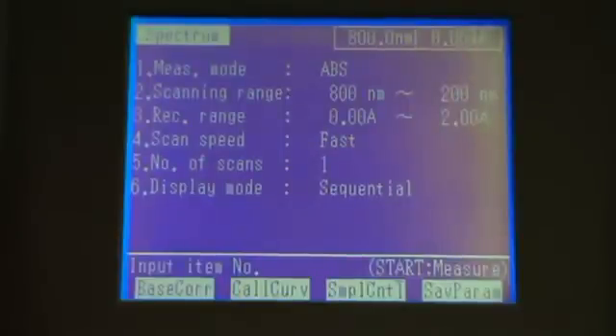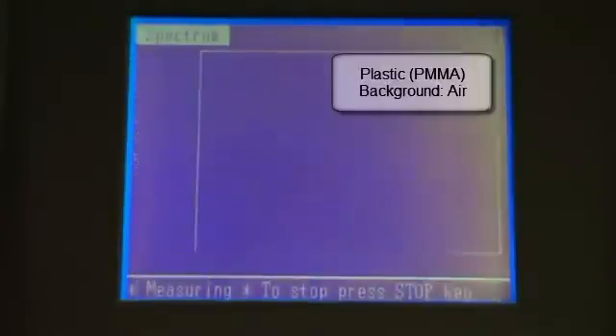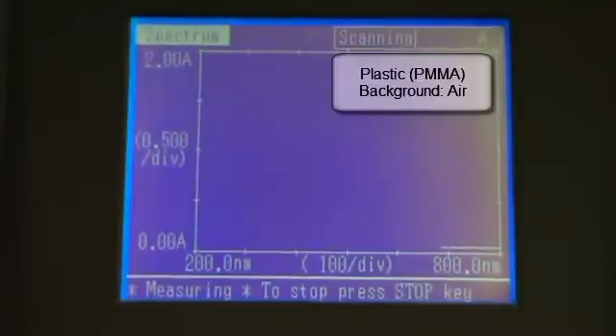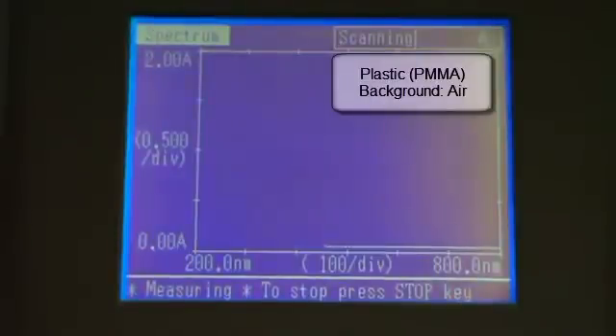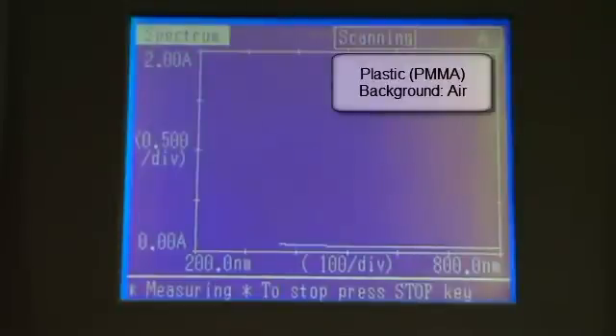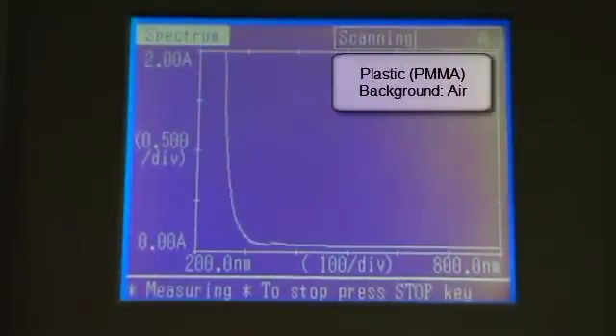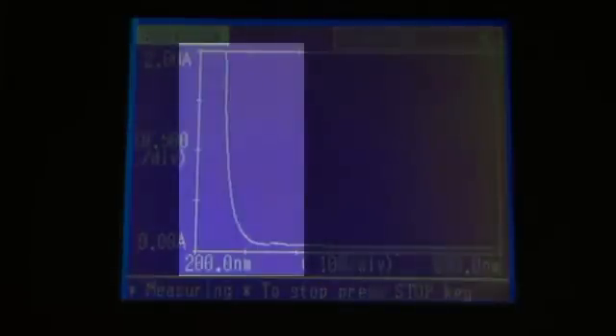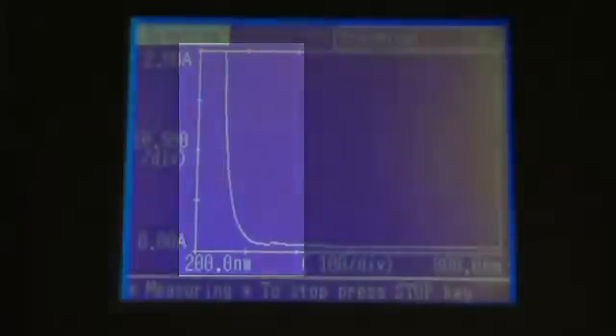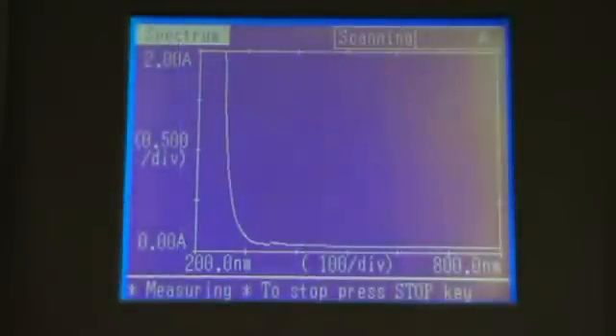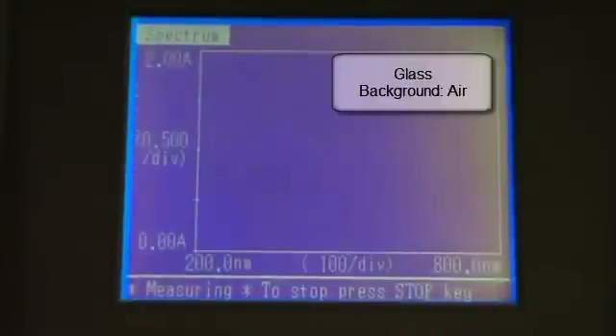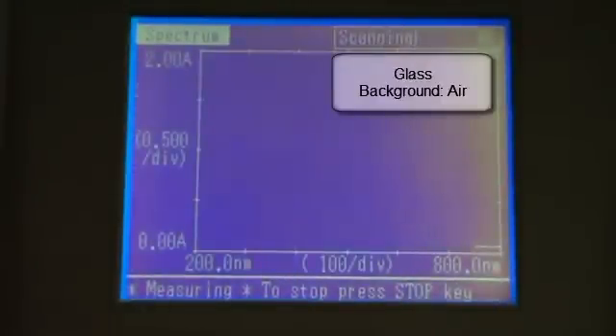In this section, we look at where each of these cells absorb. We want to select the full UV visible range, so 200 to 800 nm is entered. First up is the plastic cell. These are cheap disposable cells. We see that it has a cell window right across the visible range. It does not absorb in this region. But when we get into the UV region, the cell absorbs strongly. It cuts off. We call this the cut off wavelength. And it means that the plastic cells, which have a cutoff wavelength of about 300 nm, can only be used for samples which have an absorbance at longer wavelength than this.